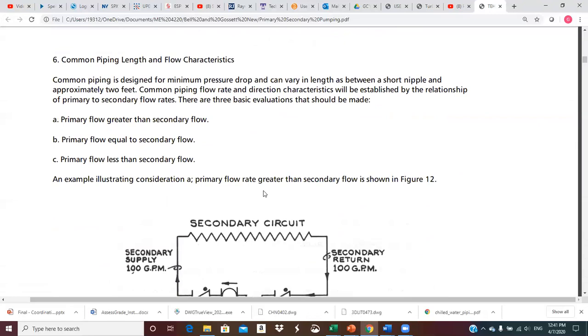Common piping length and flow characteristics: common piping is designed for minimum pressure drop — it's short — and can vary in length from a short nipple to approximately two feet. Common piping flow rate and direction characteristics are established by the relationship between primary and secondary flow rates. The three basic evaluations are: primary flow greater than secondary, primary flow equal to secondary, and primary flow less than secondary.